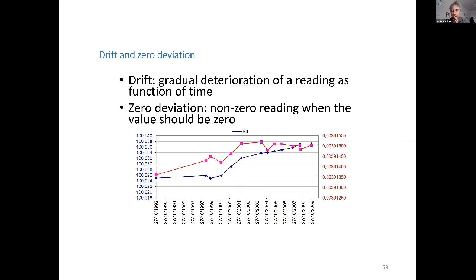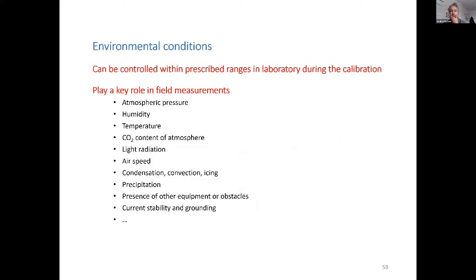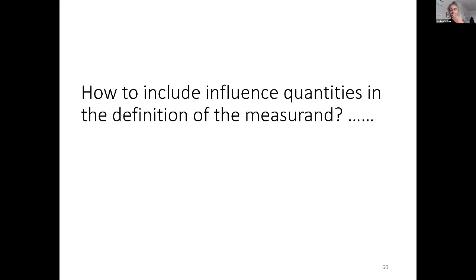This drift is so small that it can be hidden somewhere, but for some reason, it may be of the same order as the small quantity you want to detect, and you don't know it. Check for that. Do a recalibration. Do a validation or verification sometimes. Environmental conditions. They are controlled in the laboratory, but they are terrible in the field. How can we include the environmental conditions when we define what I measure? I measure this, but under this condition.